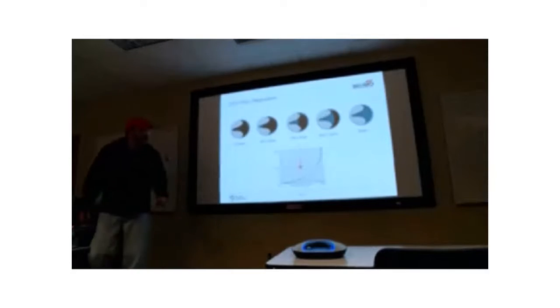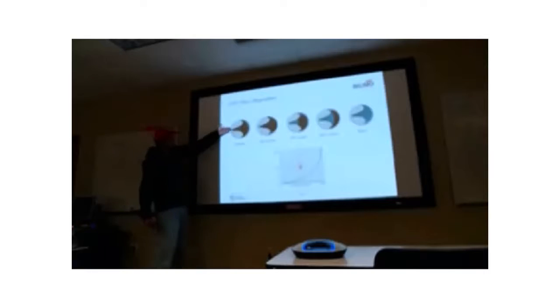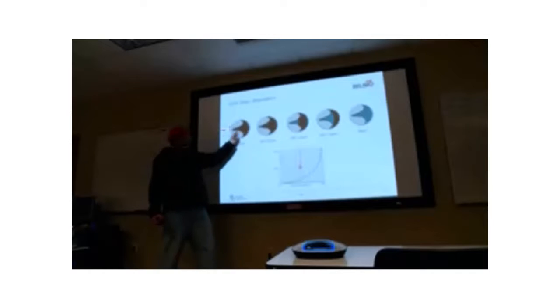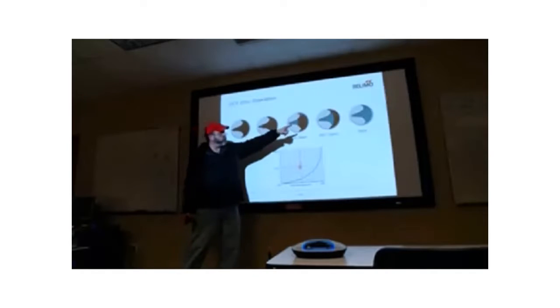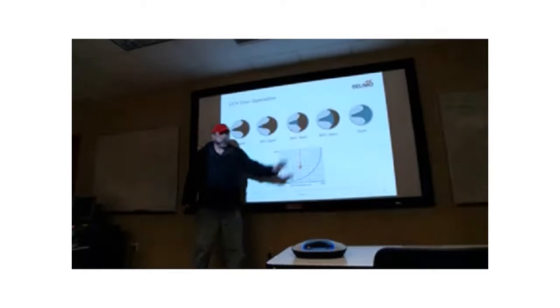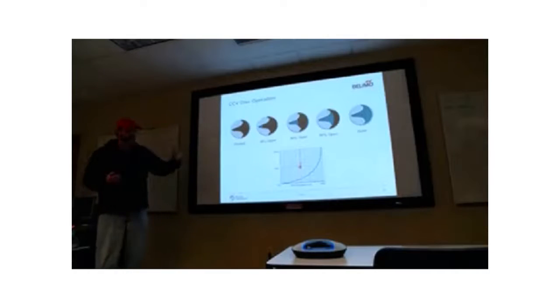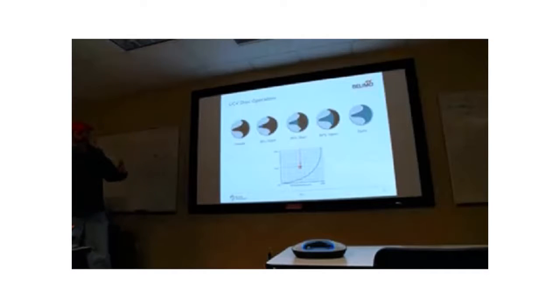This is just showing you what it looks like here. If you have the valve all the way closed and you rotate it counterclockwise, you can see more and more of the opening occurs. And this is sort of what happens to the flow. So that's that equal percentage curve that I told you about, and that's how we get it.